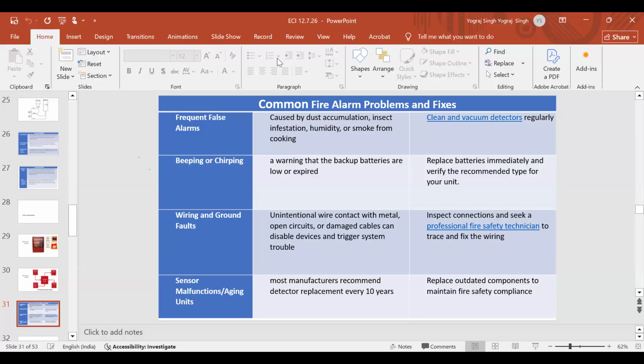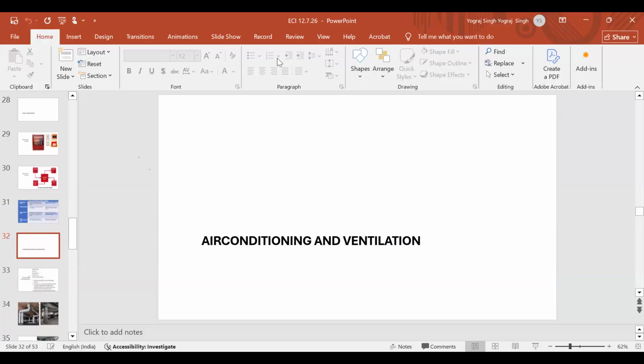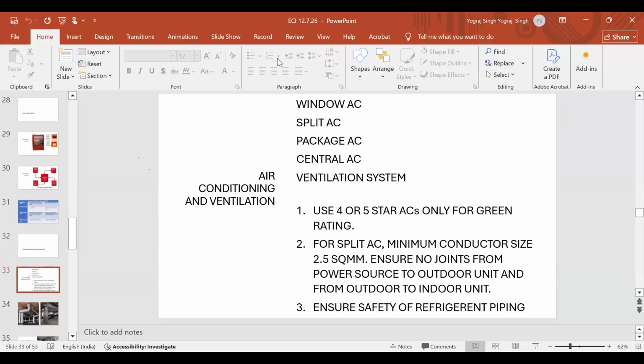Now, air conditioning and ventilation. Here I am not talking of a central AC plant or package AC plant, but you can consider a township or a multi-storied building where split ACs or window ACs are generally used. If I start talking about those AC plants, it is a big engineering subject in itself, and time will not be sufficient. Now, whenever ACs are put, you must put at least a 4-star AC. Nowadays, nobody should be allowed to use a 3-star AC because the efficiency is low. It will heat your wiring system more.